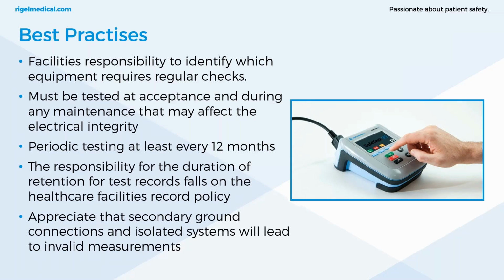So best practices, it's the facility's responsibility to identify which patient care related electrical equipment requires regular checks. Each device must be tested in accordance with NFPA 99. It's done at acceptance and during any maintenance carried out on the equipment that may affect the electrical equipment. I mean, best practice really is every time you open up a unit and make any changes, any amends, you carry out an electrical safety test.